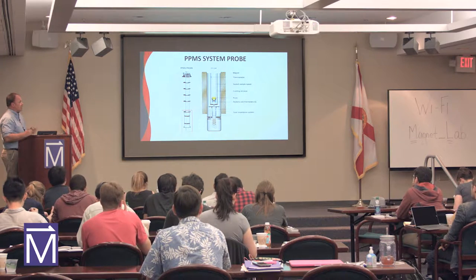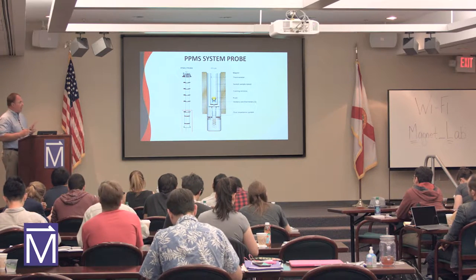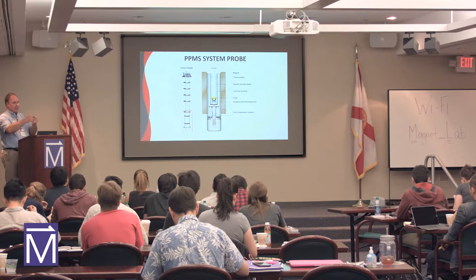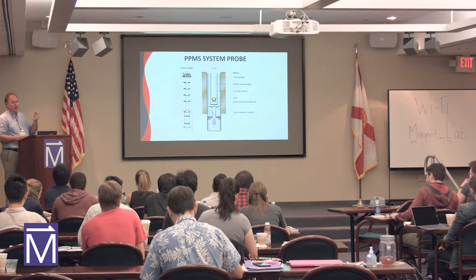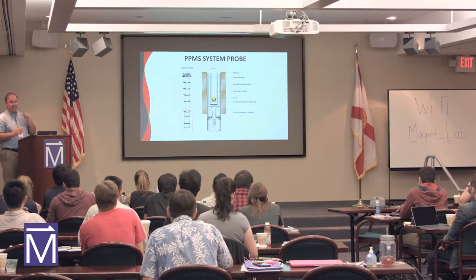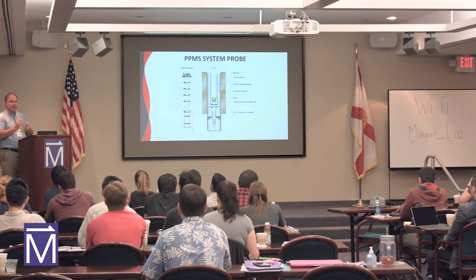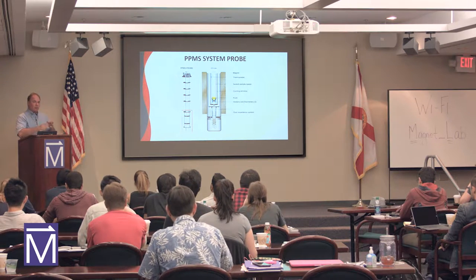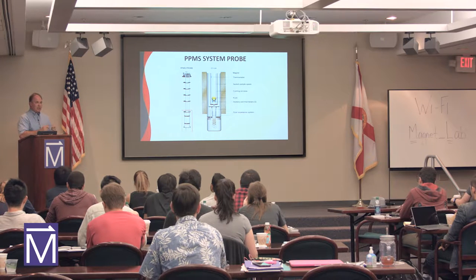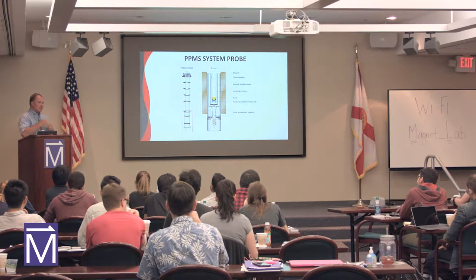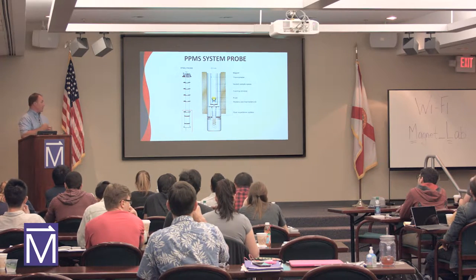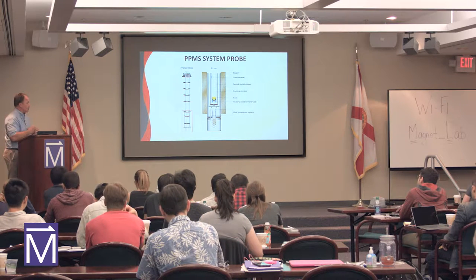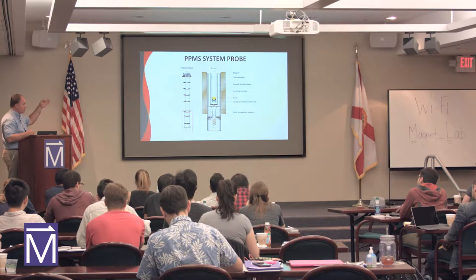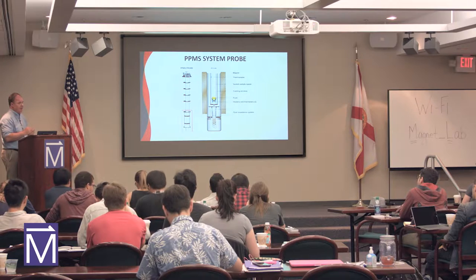So the puck sits at the center of the magnetic field. We know where that center is, so it's at the top of the platform on the transport puck. If you have a 16 Tesla system, there's a slight difference in that center, and we put that out in an application note. So there's a 16 Tesla system here, so we know where that field center is for those measurements. So essentially, this whole probe fits inside the PPMS system.